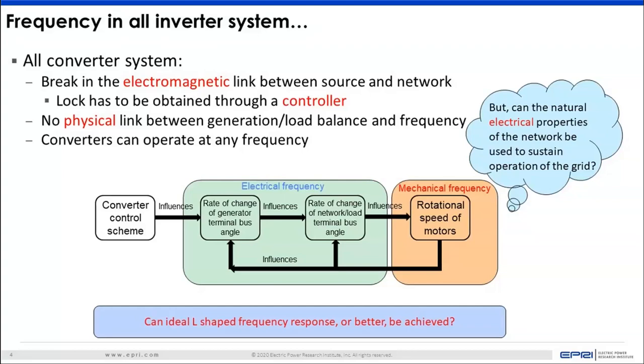So even if this structure remains, what got us thinking is: can we use these natural electrical properties that are there in the network, with respect to the fact that you still have electrical frequency changing, you still have a rate of change of angle that occurs when you have a change in load? And because converters are a faster resource, because they have lower mechanical time constants, of course, recognizing that wind turbines will have a mechanical time constant, but it will be smaller compared to a large thermal plant. And of course, solar PV and battery energy storage would not really have large time constants.